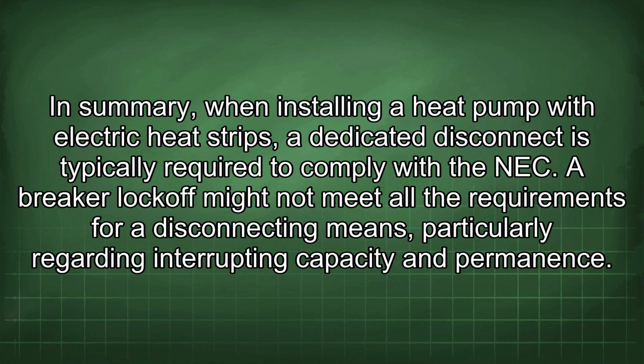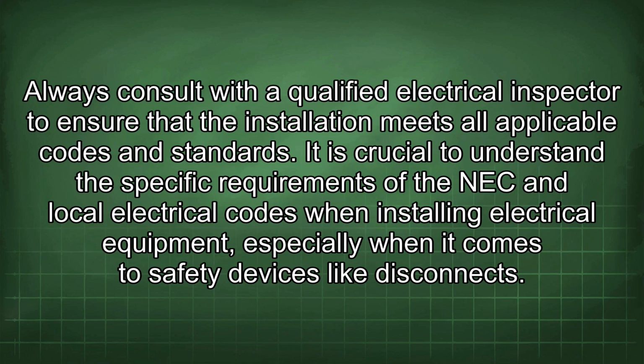In summary, when installing a heat pump with electric heat strips, a dedicated disconnect is typically required to comply with the NEC. A breaker lockoff might not meet all the requirements for a disconnecting means, particularly regarding interrupting capacity and permanence. Always consult with a qualified electrical inspector to ensure that the installation meets all applicable codes and standards. It is crucial to understand the specific requirements of the NEC and local electrical codes when installing electrical equipment, especially when it comes to safety devices like disconnects.